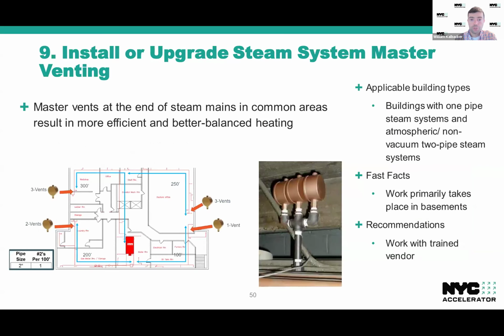Measure number 9 is to install or upgrade master venting on steam systems. So steam systems, when they're in between cycles, the distribution is going to fill with air. And when the boiler fires back up on its next cycle, the steam that it produces during the next cycle needs to work against that air and push it out of the system before the steam can get to all the radiators in the building. And the harder it is for that air to escape the system, the harder that steam has to push and the harder the boiler has to work to get that air out, which means that you're using more energy and fuel than you need to.